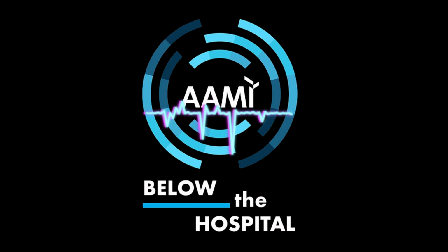And I haven't mentioned this yet. The ISO standards for radiation are under review right now. Just last year, 2025, we finished a significant revision of 11137-1, and we're in the thick right now of a revision of part 2 of the radiation standard, 11137-2. And in both part 1 and part 2, we're adding content to help provide the industry with the science behind limits of detection in bioburden tests, sensitivity in bioburden tests, how you can improve the sensitivity, or how you can deal with sensitivity if for some reason it's just not possible to get a more optimized bioburden test.